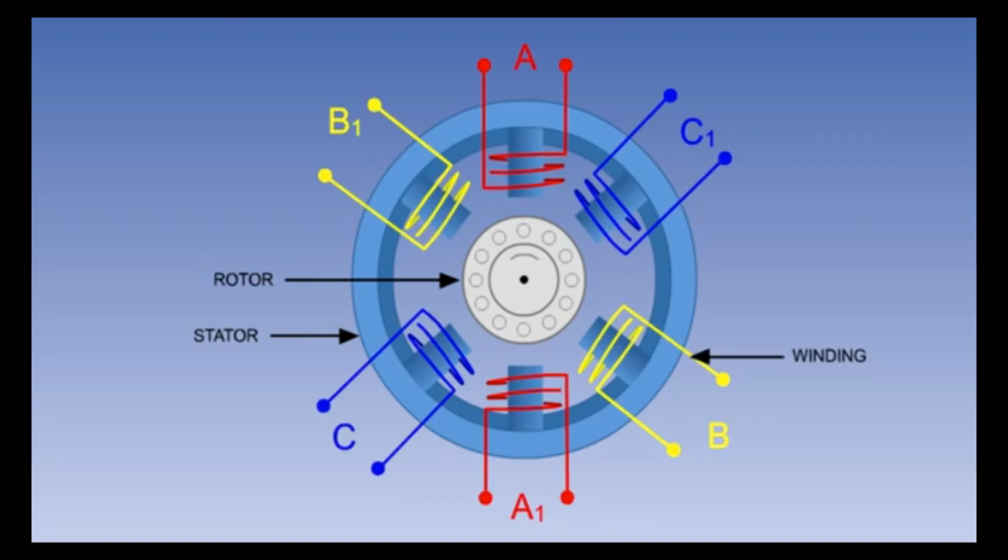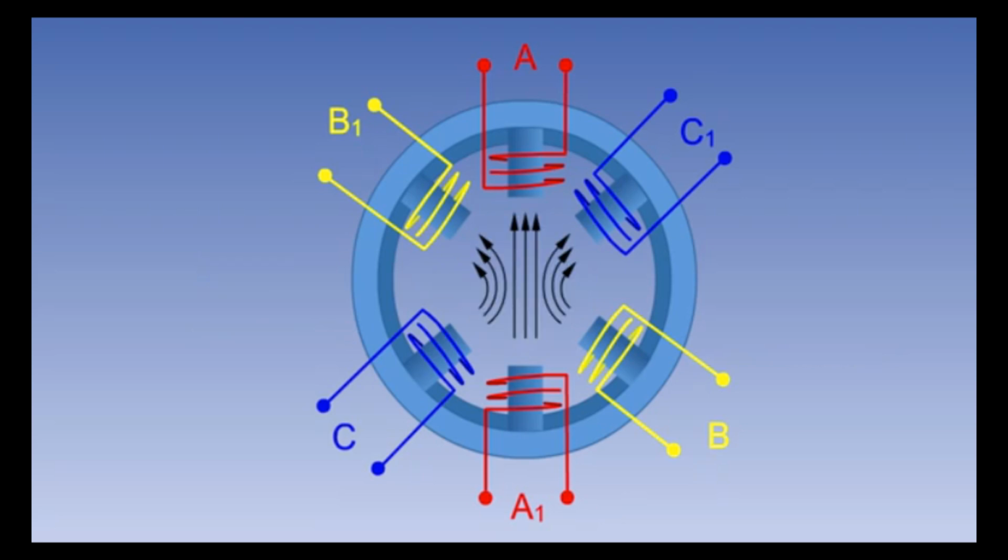The stator is most commonly fed from a three-phase AC supply. The stator windings are set 120 degrees apart, with the pair of poles for each winding being supplied from one of the three phases. This arrangement produces a rotating magnetic field around the stator.